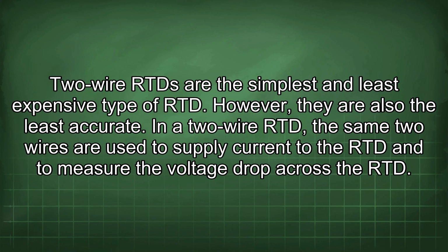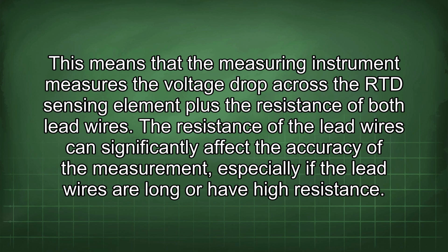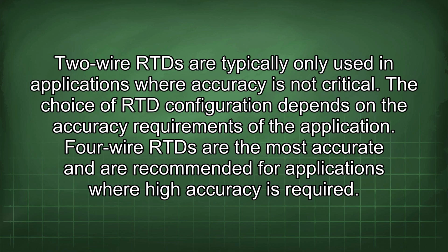In a 2-wire RTD, the same 2 wires are used to supply current to the RTD and to measure the voltage drop across the RTD. This means that the measuring instrument measures the voltage drop across the RTD sensing element plus the resistance of both lead wires. The resistance of the lead wires can significantly affect the accuracy of the measurement, especially if the lead wires are long or have high resistance. 2-wire RTD are typically only used in applications where accuracy is not critical.